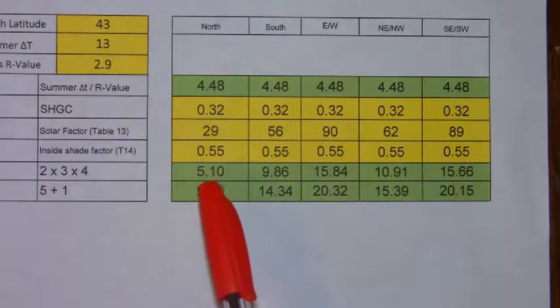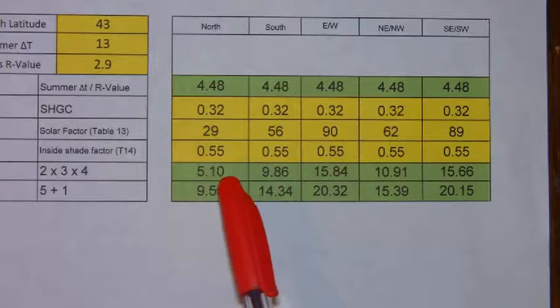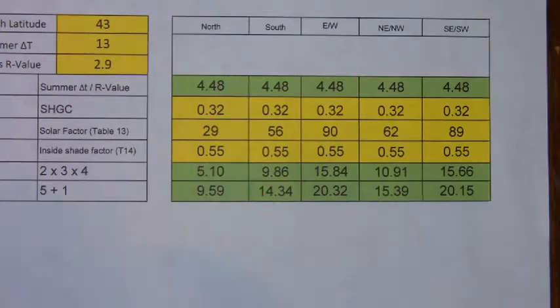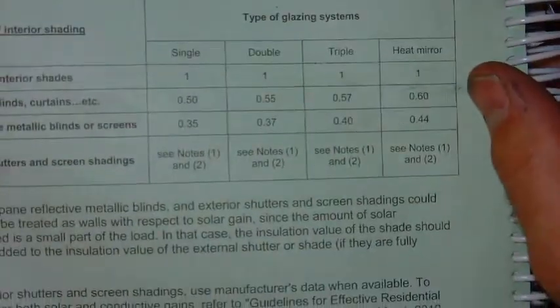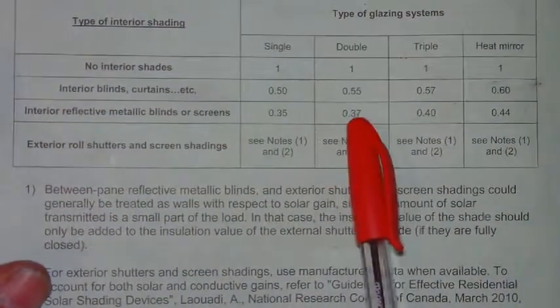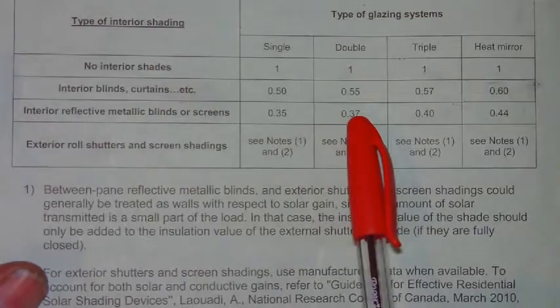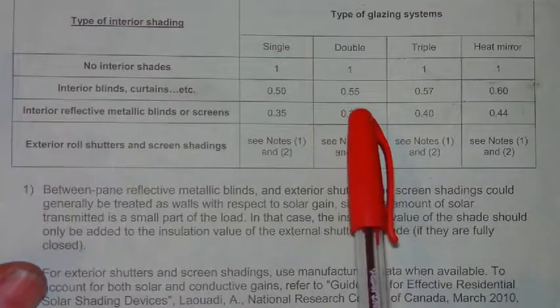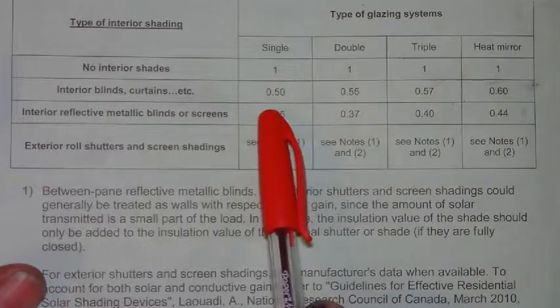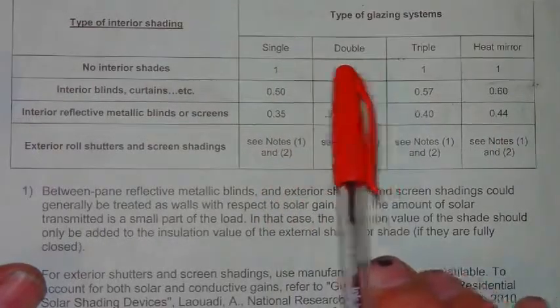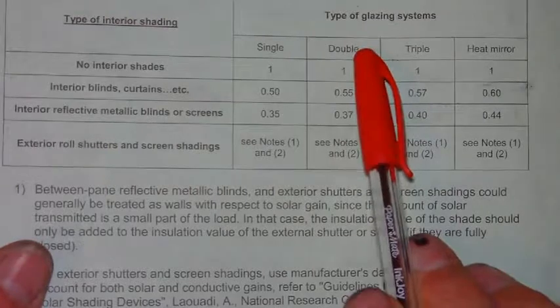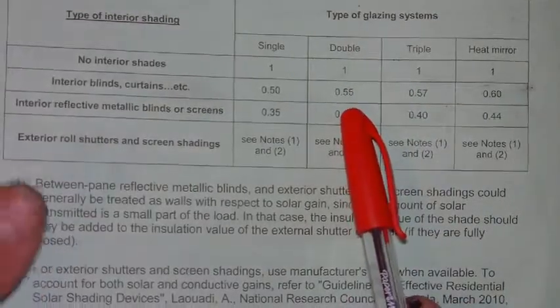The inside shade factor is determined by whether or not you have interior shading such as drapes or blinds. In our case, we have decided that we are using interior drapes or blinds. For a double glass window, the factor is 0.55. If you have no interior shading, then you would use 1. Note that the internal shading factor changes for different window types — single, double, triple. So in our case, we are using a double glass window, so you are going to use a value of 0.55.